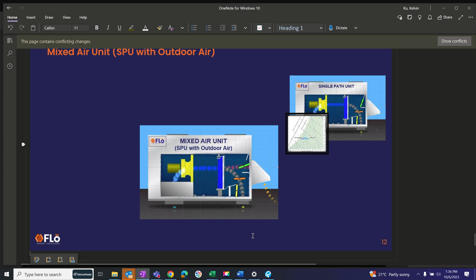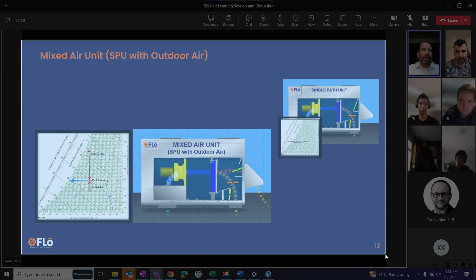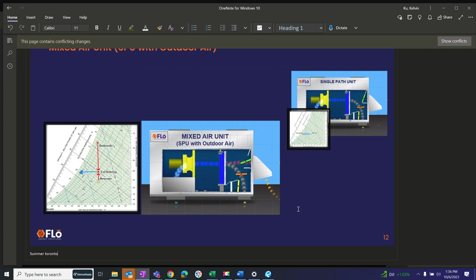Essentially, you bring in some outside air, it mixes, then goes across the coil and returns to the space. What's interesting in the psychrometric chart is that the outside air—this example is from Toronto, on a peak day—is really hot and quite humid, over by the saturation line. Your return air from the store is down here. When you mix them together, this hot, humid air is pulled down, actually away from the saturation line. It's mixed, and then both air streams go through the coil and are cooled.